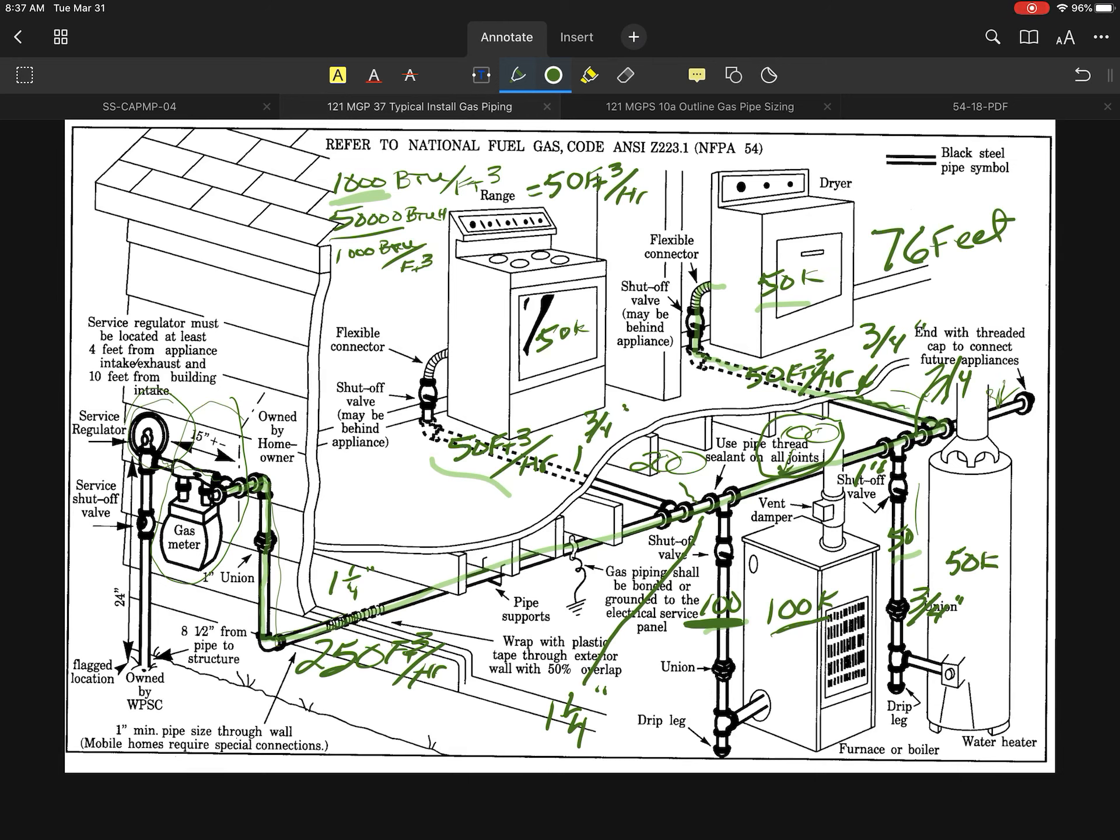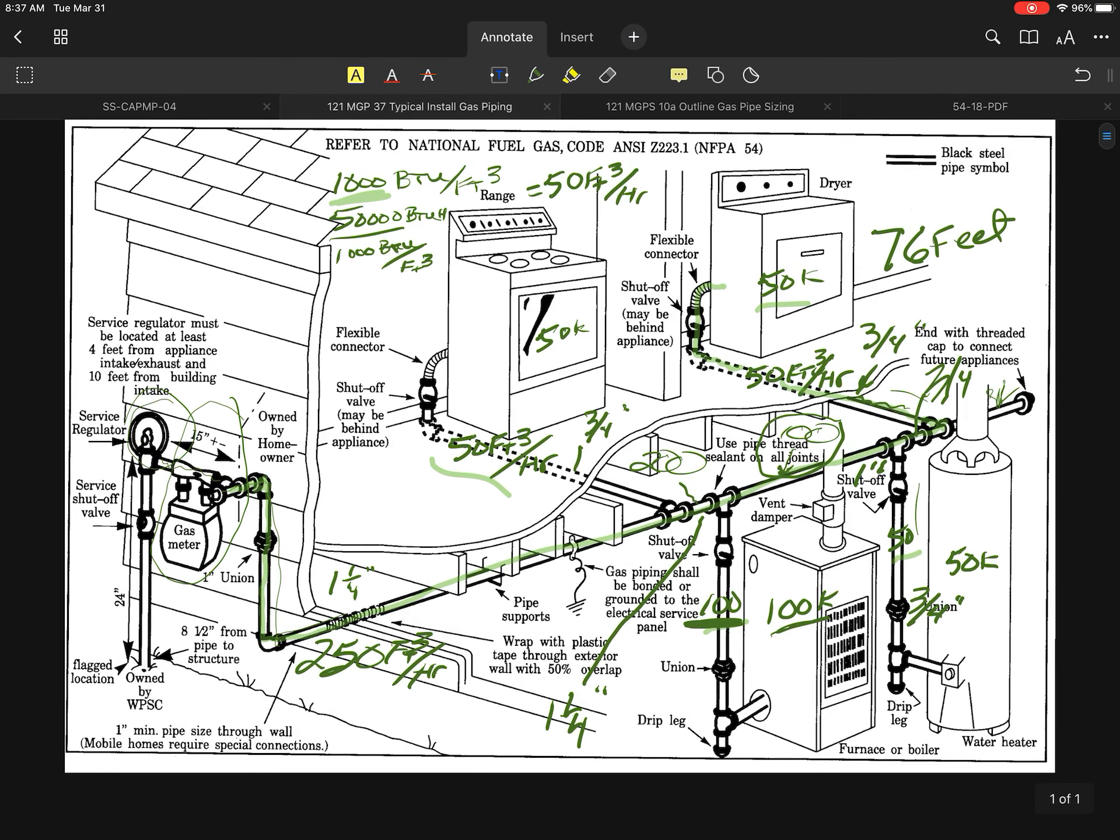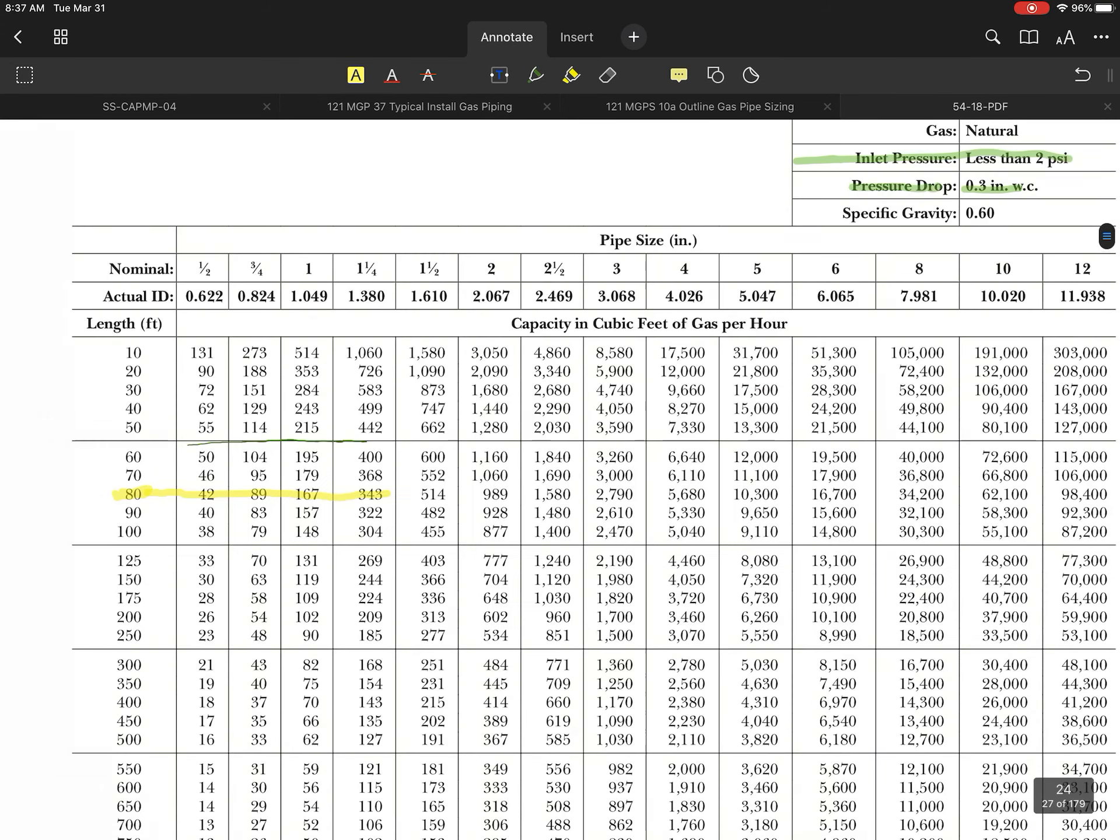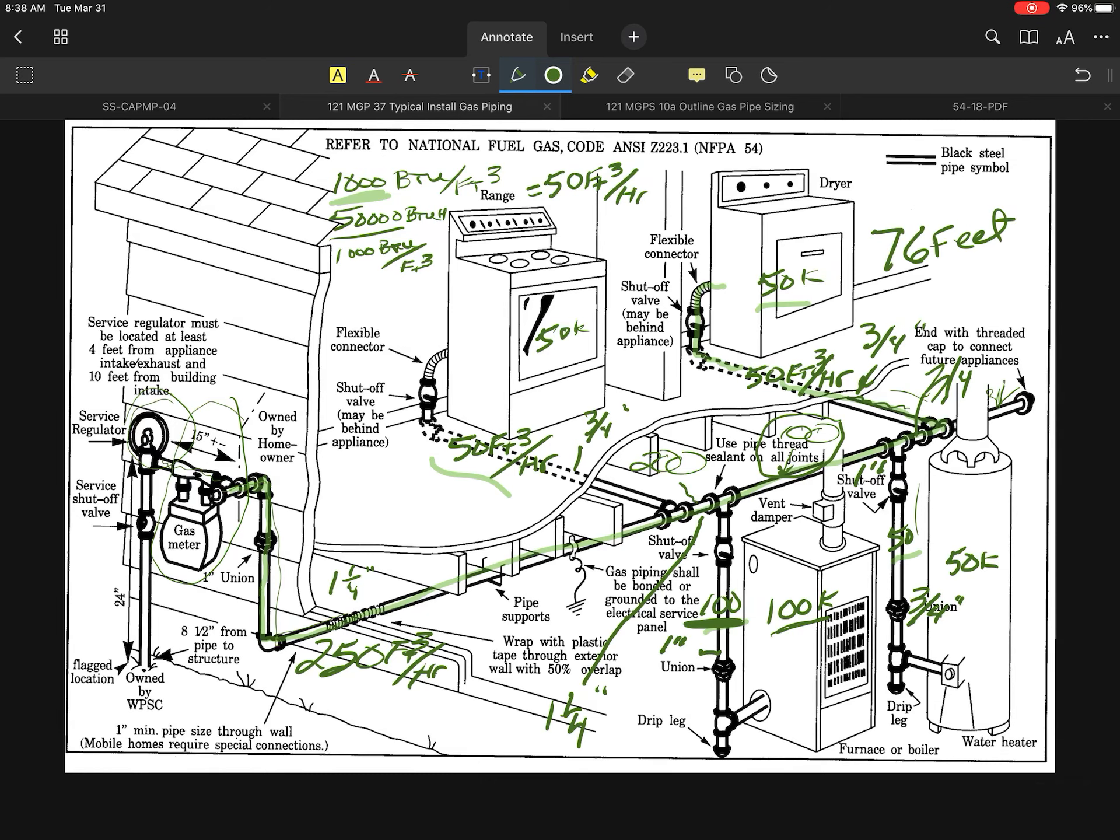For my 100,000 BTU boiler, I want to look at that one. That one's going to have to be a 1 inch. The 1 inch is going to carry 167. So this line right here would have to be a 1 inch line that drops down to that boiler from the main.